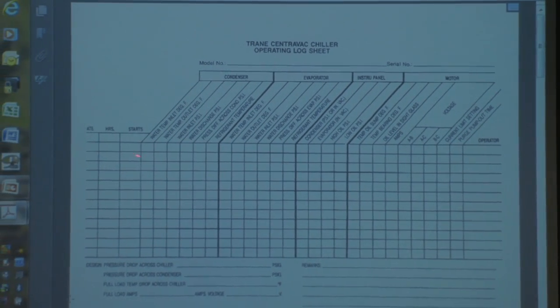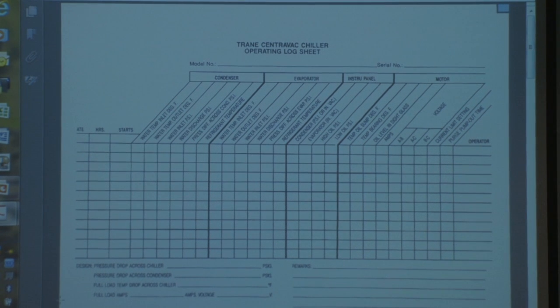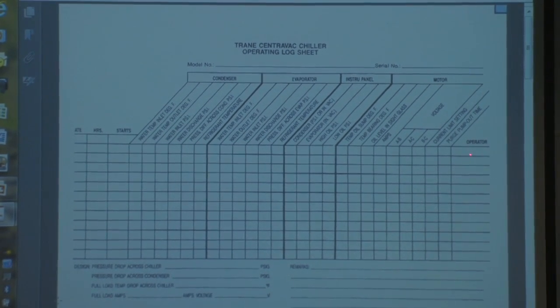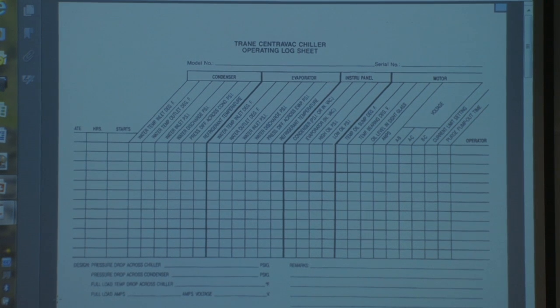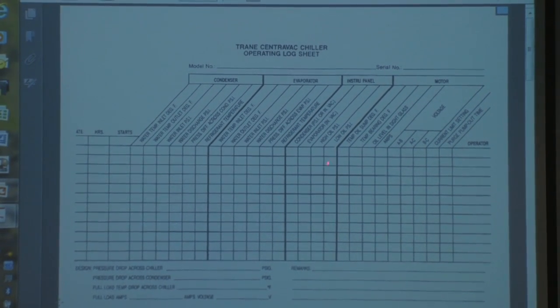Number of run hours, number of starts, and the collection of data that we'll talk about in a little bit here. And if there's any comments you want to make, you know, it was noisy or something, you can put it down there. Each day is another line, so you can just look right down here and see trends. That's why someone made the comment, well, now they have this on computer. What I've seen is a lot of manufacturers have a printer interface capability where you can download a report that has all that information. But you get all these strips of data in a big pile in a file folder, and you can't see them all in one place. You just can't see trends because they're not all lined up together. So there is an advantage to having a daily log sheet. Usually people print out several of these and put them on a clipboard on the chiller.